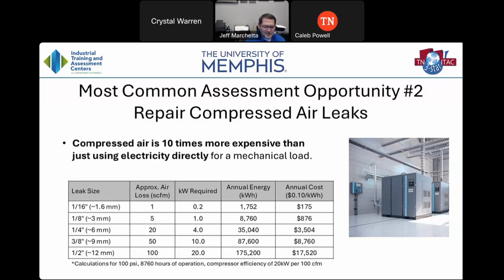So when you hear these hisses, those are the ones that you should fix, because if you hear it, that means it's got decibels in the audible range. There are probably a lot more leaks that you can't hear. So if you can hear it, that should be very high on your list for repair. Okay, we'll talk about how you find the ones that are more difficult to hear, and some of them are simply difficult to hear because you're in an environment, in a plant that might be producing, that the noise is overshadowing the noise of the hissing that's coming from the line itself.